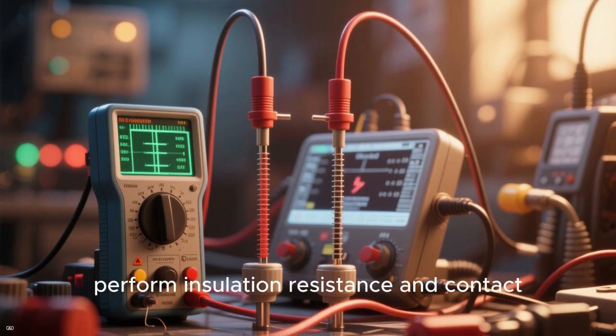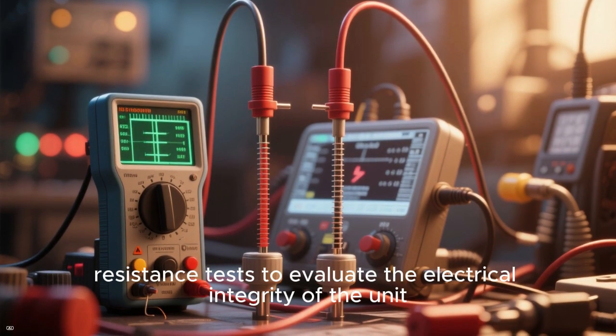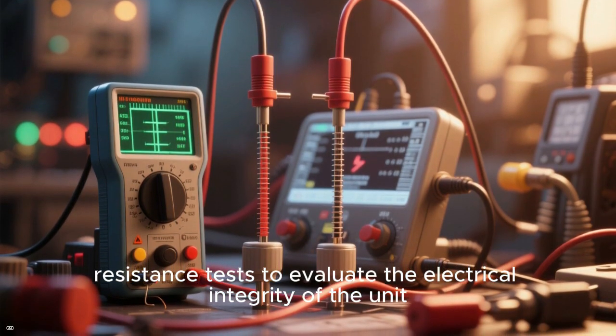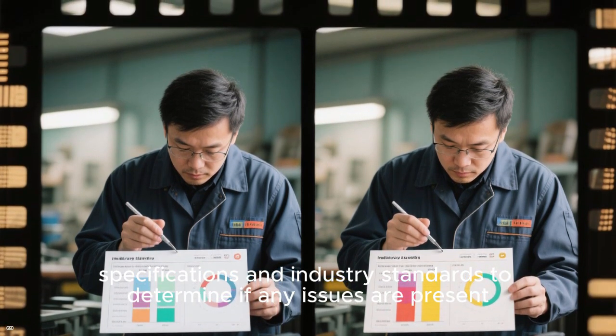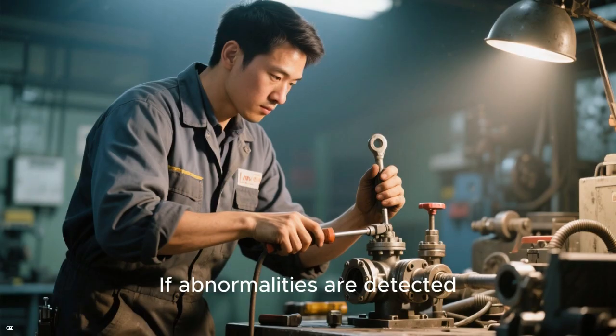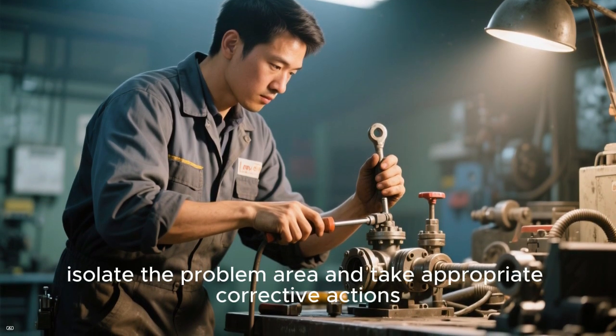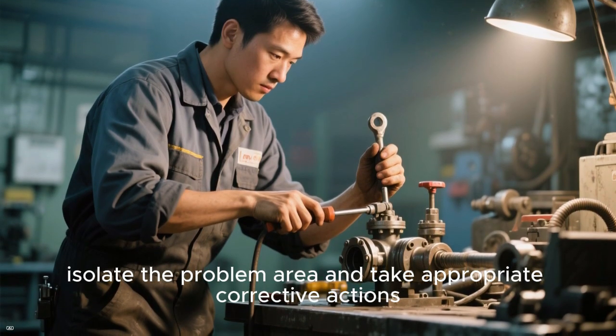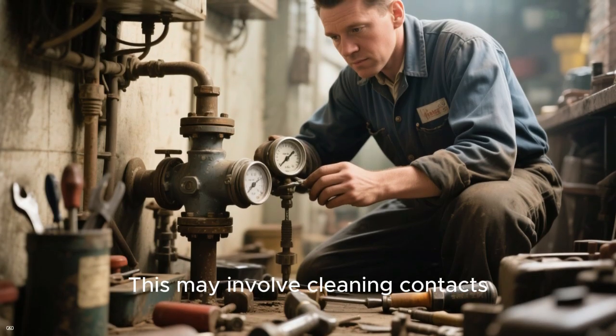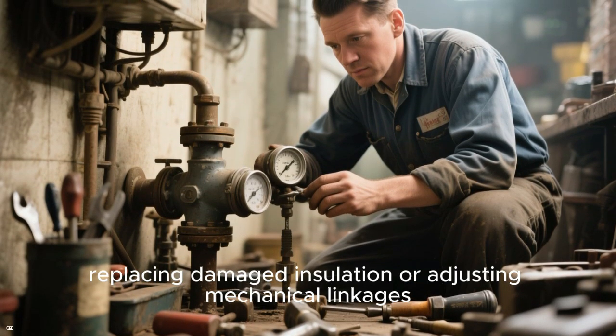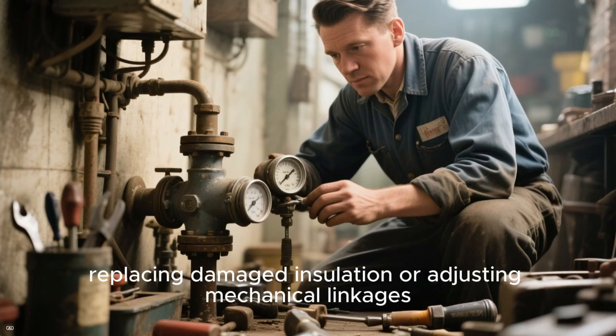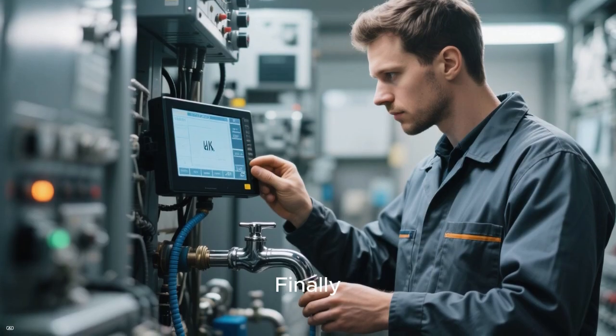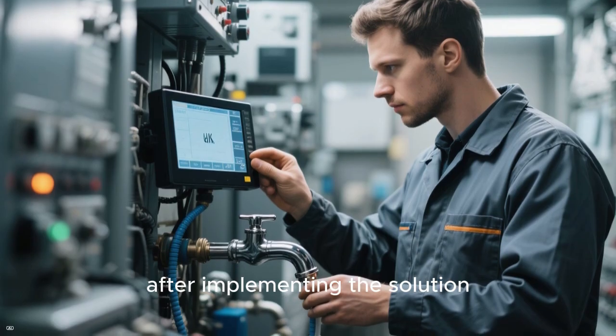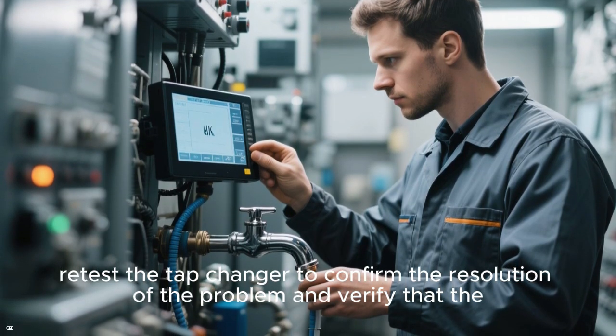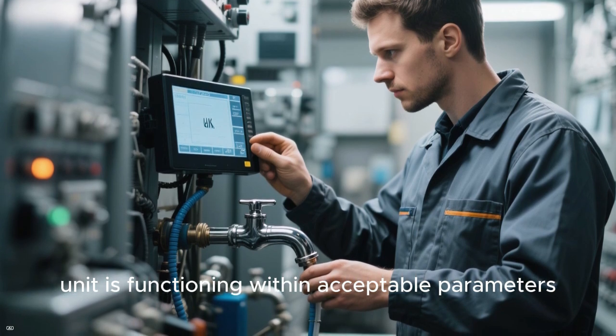Next, perform insulation resistance and contact resistance tests to evaluate the electrical integrity of the unit. Compare the test results with established specifications and industry standards to determine if any issues are present. If abnormalities are detected, isolate the problem area and take appropriate corrective actions. This may involve cleaning contacts, replacing damaged insulation, or adjusting mechanical linkages. Finally, after implementing the solution, retest the tap changer to confirm the resolution of the problem and verify that the unit is functioning within acceptable parameters.